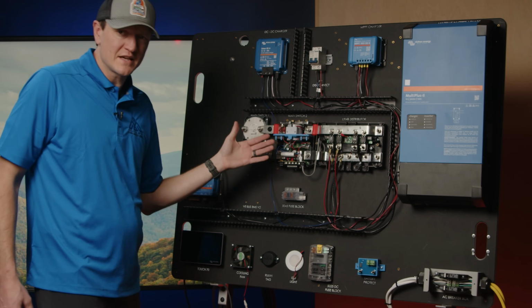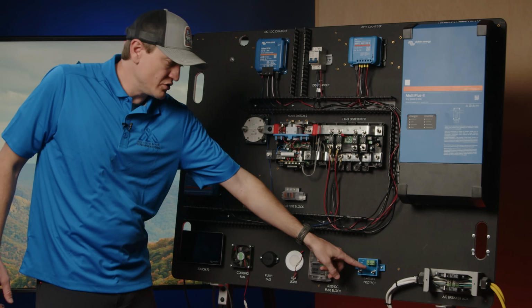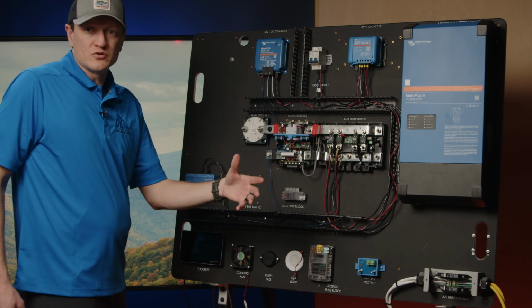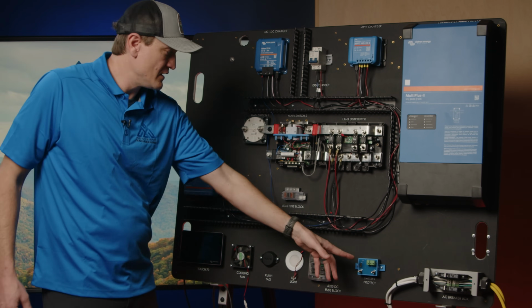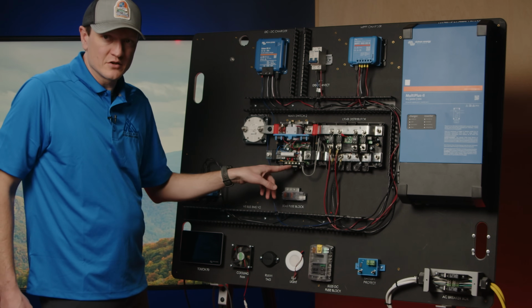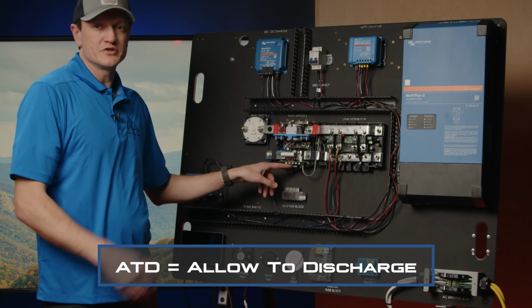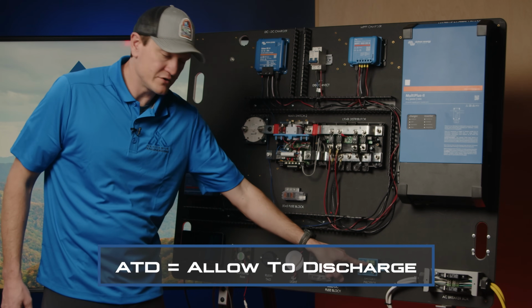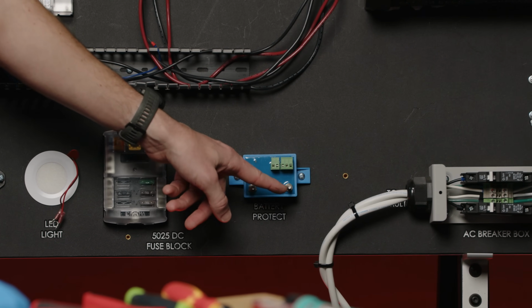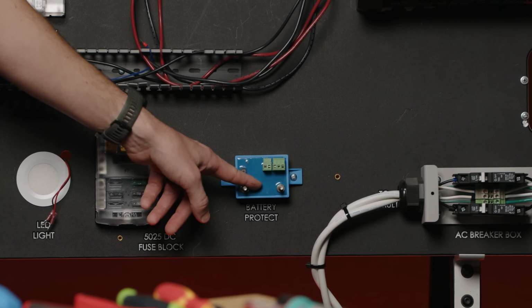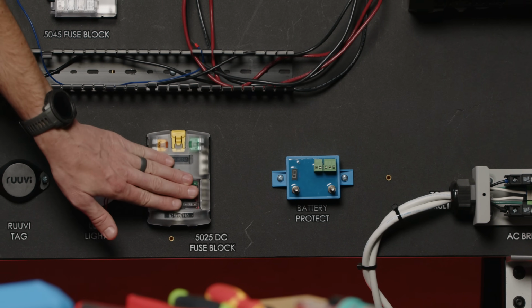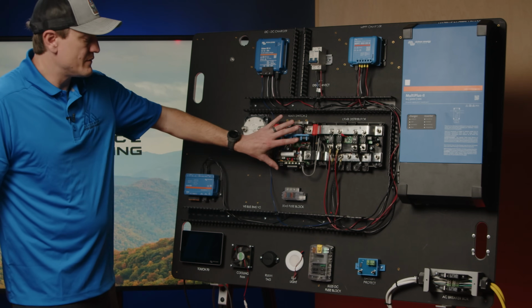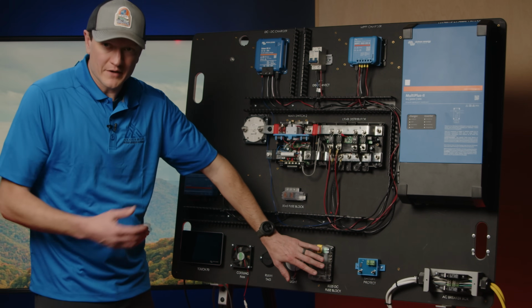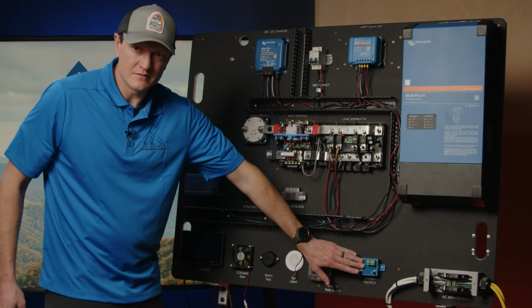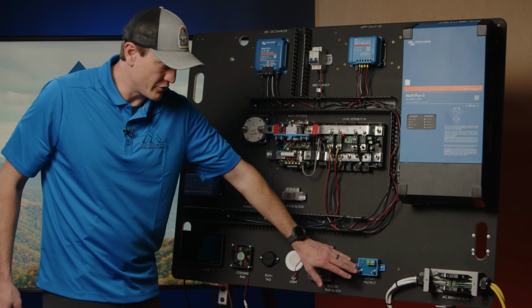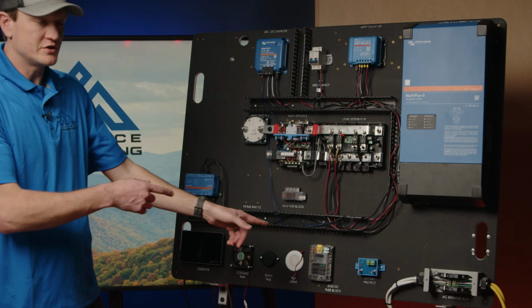Okay, the BMS has the ability to control this device using the remote port by sending voltage or not sending voltage to the high side coming off of the ATD port here. So the ATD port stands for allow to discharge. And so we're going to run a communication wire from here down to the H on this remote switch. And that is going to tell this to turn on or off, which is ultimately going to control all of the loads that are connected to this DC bus bar. So if the BMS doesn't want any more power coming out of the batteries, then it's going to tell this guy, hey, stop allowing power to flow through to the DC bus bar. And so it's going to switch that device off.